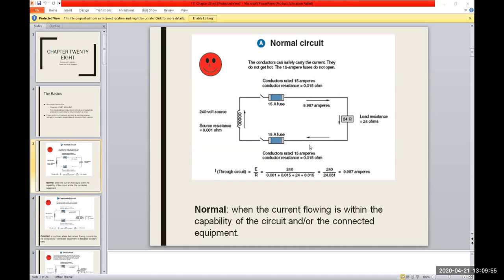Now notice they have a couple of little additions in there besides the 24. If you look at that sub note, it says the conductors that are rated at 15 amp, you do have conductor resistance. Typically, wire is a pretty low resistance, and you can see there, 0.015, but there is a certain amount of resistance to it. So you plug it all together, put in your formula, and come out with how much current is running through this circuit. Well, you have 9.987 amps. Crazy number, but that's just how you would go through it.